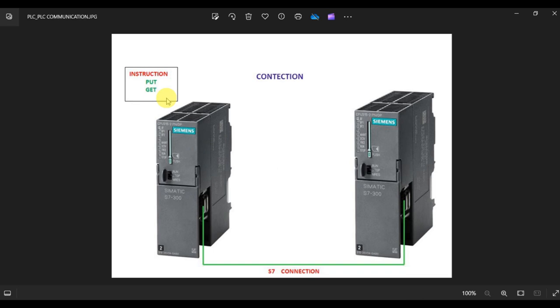Using LifeBit, let's say the LifeBit of PLC 1 will be displayed on PLC 2's HMI. It will blink every 2 seconds, and the LifeBit of PLC 2 will be blinked on PLC 1's HMI. So this will help to easily identify the missing of a communication.